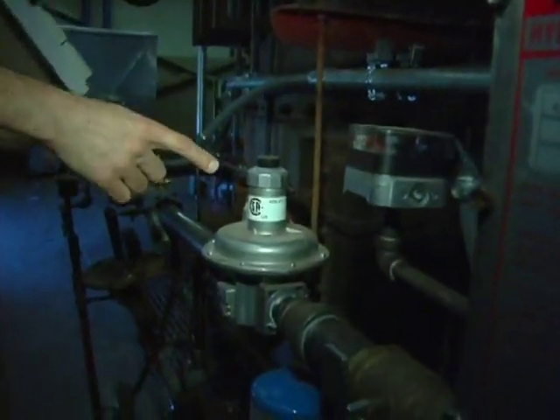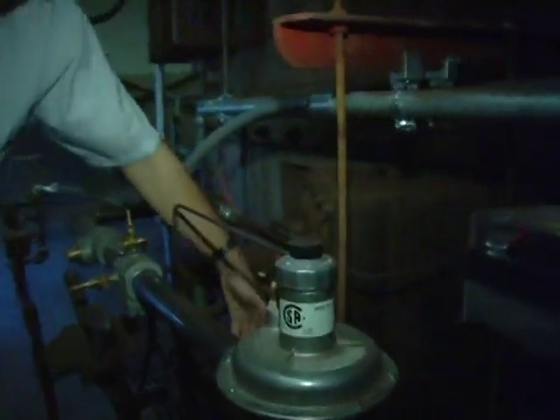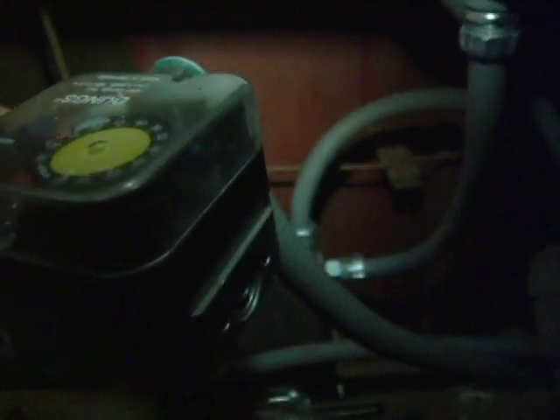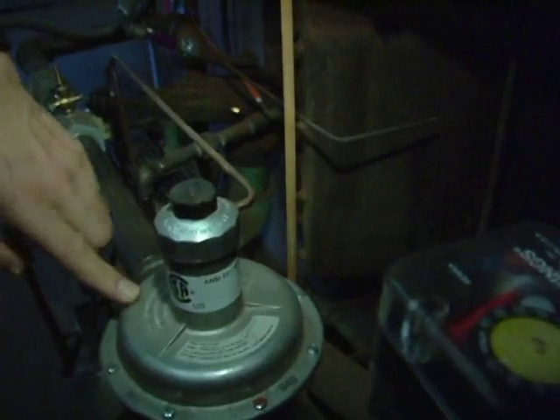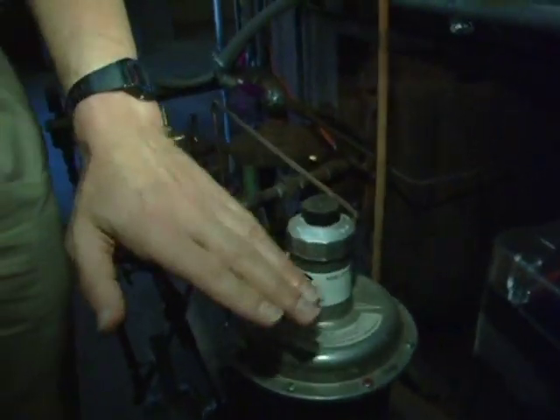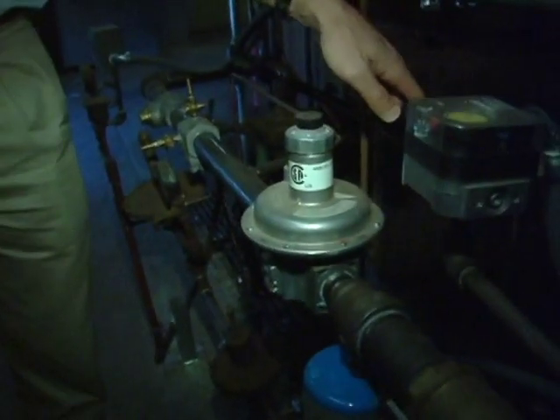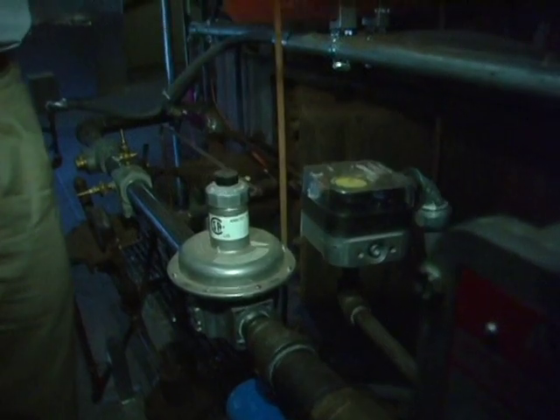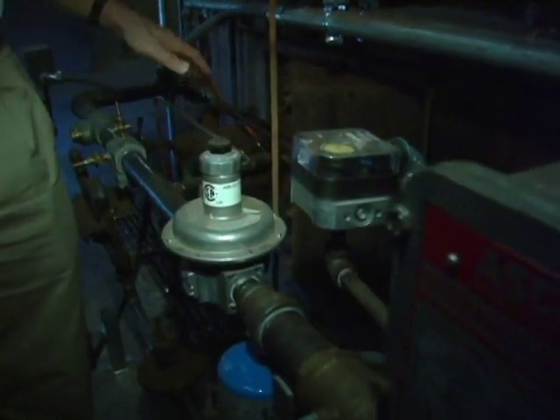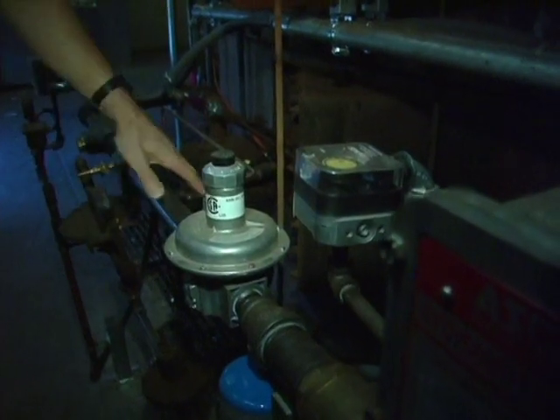Okay. It gets an impulse signal. See this line here? This line here goes to this line. That's your air line. The big 3-inch line is your air line. So, the combustion control works by modulating this airflow. First it gets a signal to modulate that butterfly valve on the air line. Changes the airflow, okay? The change in airflow is sensed as a change in pressure through this impulse line here, which goes to this regulator, modulates that damper so that it responds by giving enough gas in proportion to the amount of air, okay? So the control is first to the air line, and then the gas line responds to it. And all burners work that way, because you never want to add gas without air. You always want to have enough air. So the flow of gas responds to the amount of air.